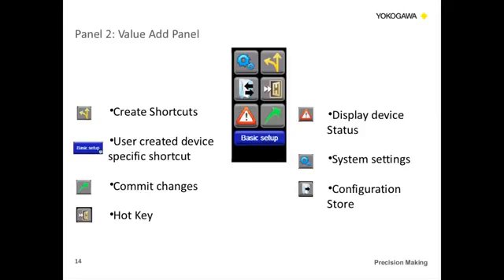A lot of times when you order transmitters, you order like 24, 50, 100 at a time, and they have the same setup, but you're just trying to change the tag number. So when you connect to the device, if you have a shortcut key with tag number, right when you connect you just hit the tag number, and you don't have to worry about the menu tree to get down to the tag number. You just press the button and go straight there.